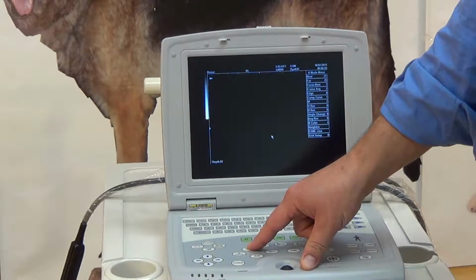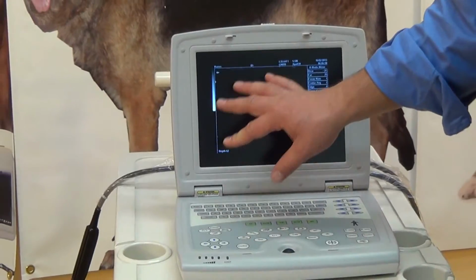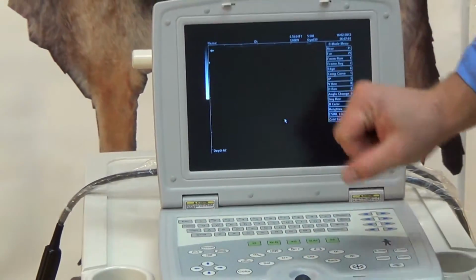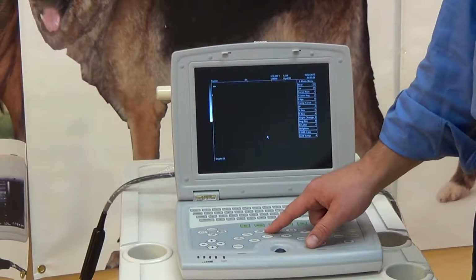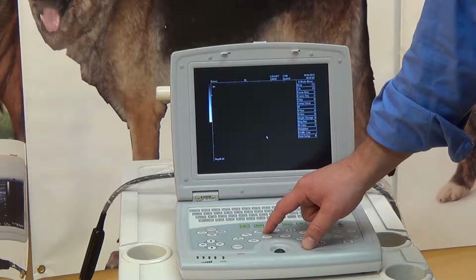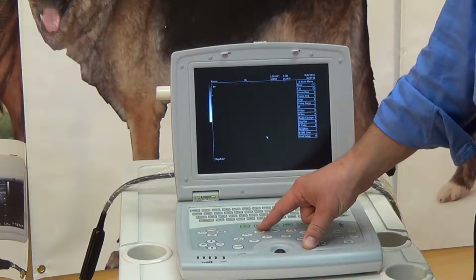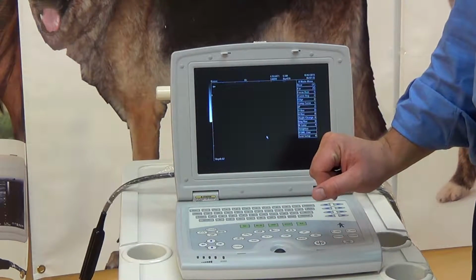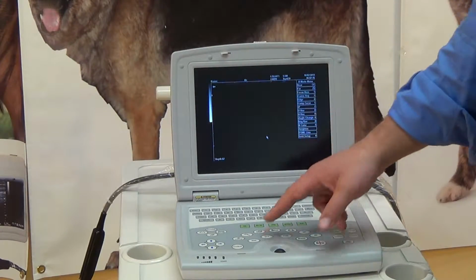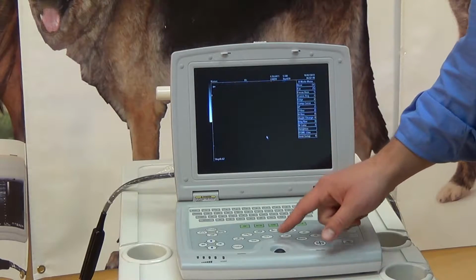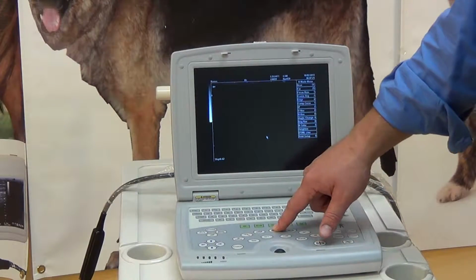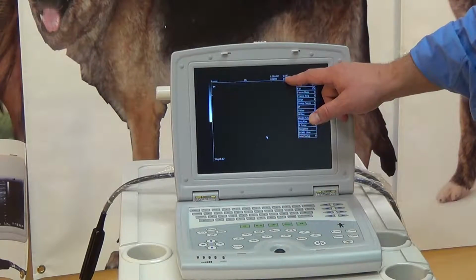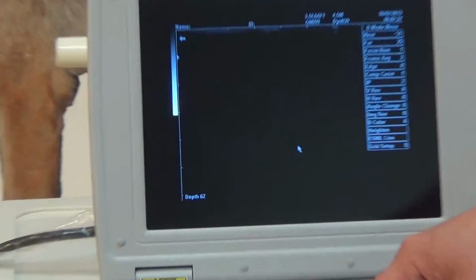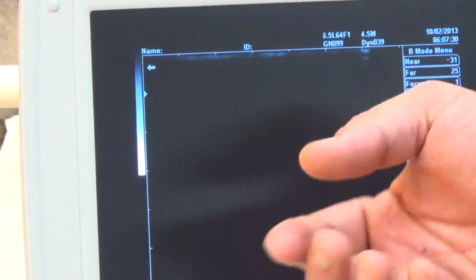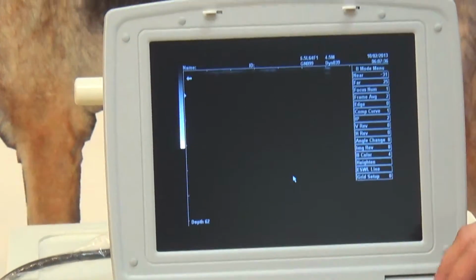This button here, magnifying glass, is somewhat self-explanatory. You zoom in. You can't really see this well here because we don't have an image, but it just does an overall zoom. This right here is a button that's used for frame compression. That's something that you can use to change the sharpness of some of the pictures, not a setting that most people use, but you can play around with it till you figure out how it works in your specific setting. This button here changes your frequency. So that is a button that most people do use, and that's signified up here. The lower the frequency, the deeper you can penetrate into the animal that you're looking at, the less resolution. The higher the frequency, the shallower you can get, but the more clear the image will be.